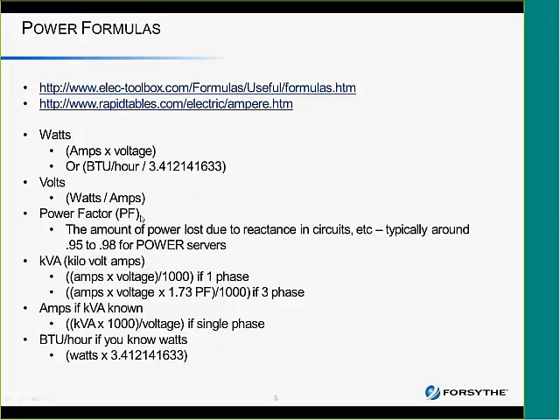There is something called a power factor that you do have to take into account, which I do use in my calculations, and that is you never ever get 100% of the power that you would expect to get, because you lose some due to reactance in the circuits. For a power server, depending on which one, it's between 0.95 and 0.98. So I usually build that into my calculations in the spreadsheet for working out some of the voltages and so on. So you'll see here that where you'd use a power factor is when you're actually calculating kilovolt amps. If they give you the amps and the voltage, and you're doing three-phase, then you use a power factor. Most of you will be doing single-phase, so it shouldn't be an issue.